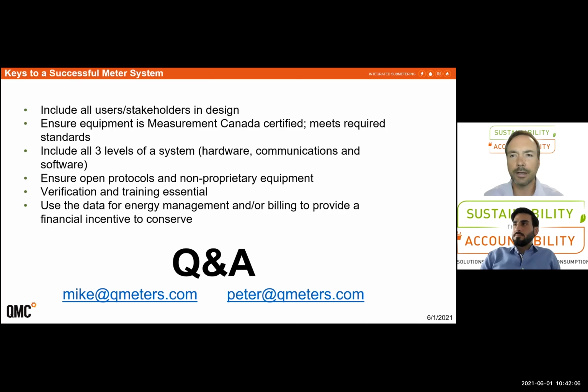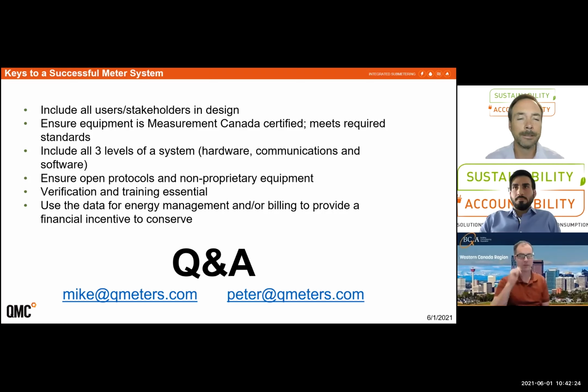So when you're designing a good meter system, look at including all of your users and stakeholders in the design process. Ensure that all of the systems that you're designing do meet Measurement Canada requirements if it is for billing, or other local standards such as safe drinking water codes for water meters. Include all 3 levels in your system design: hardware, communications, and software. Without addressing all 3 of those components, you will not have a complete meter system. Do ensure open protocols and non-proprietary equipment so any group can access that meter data.